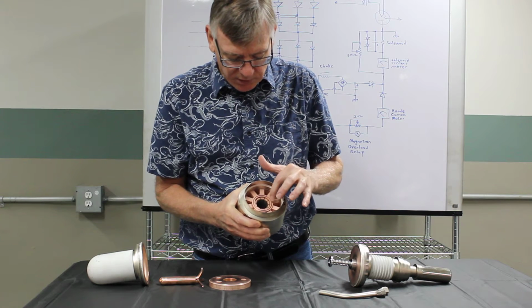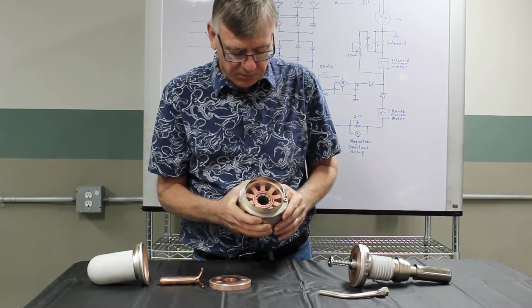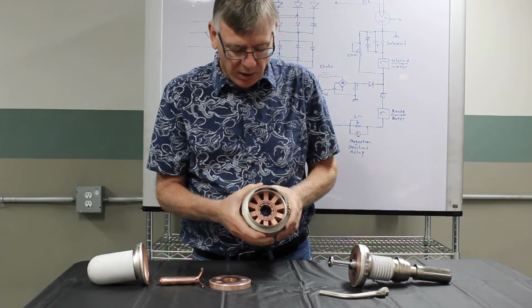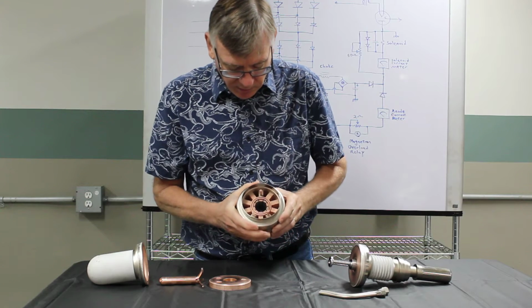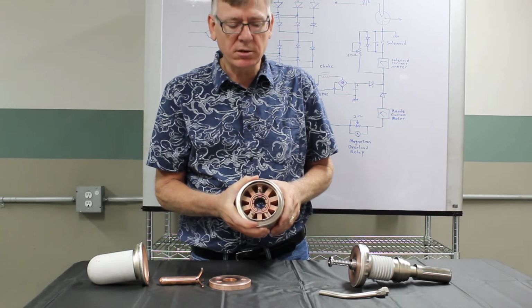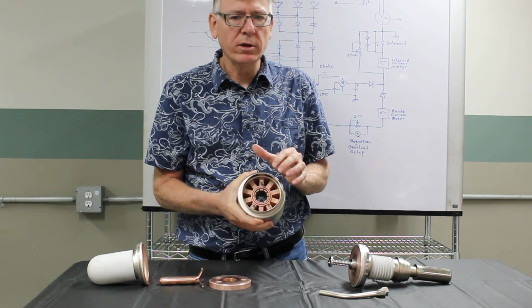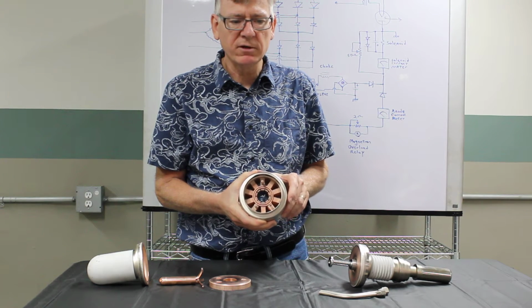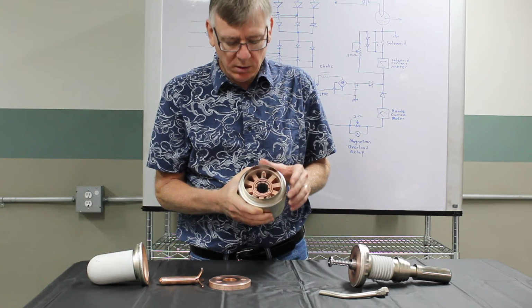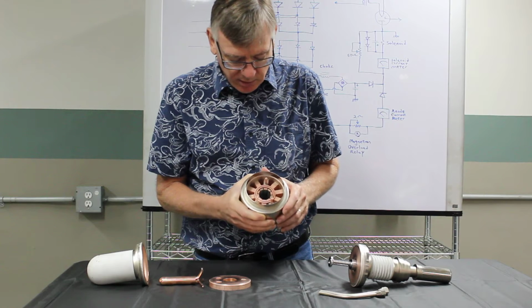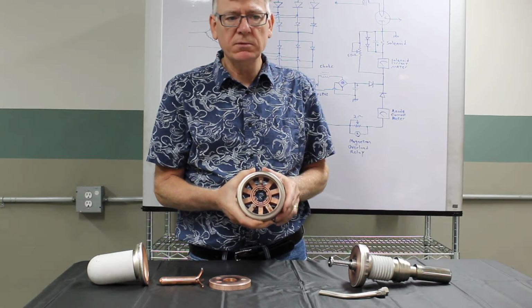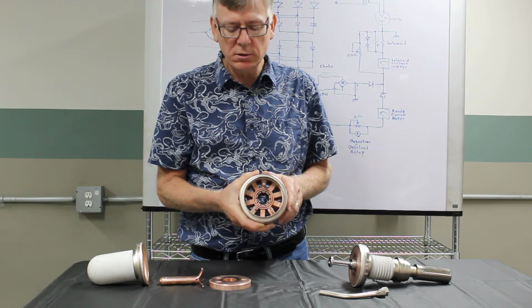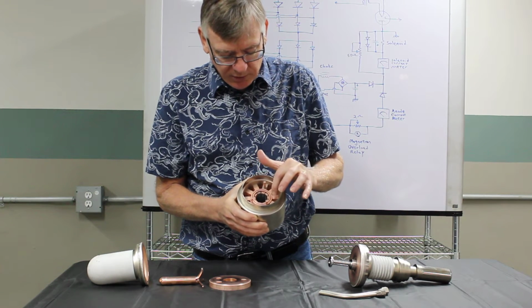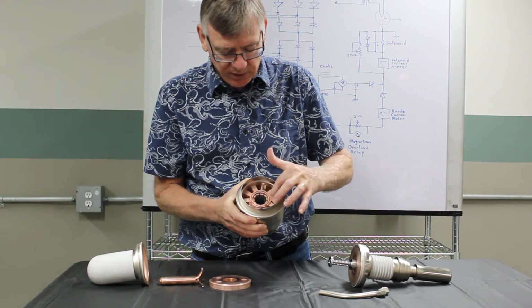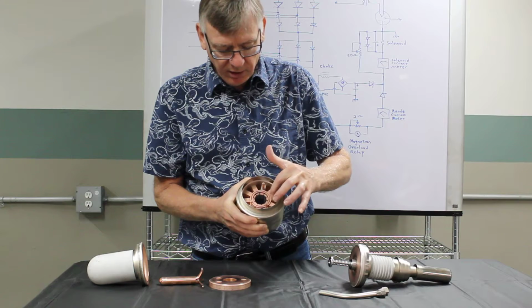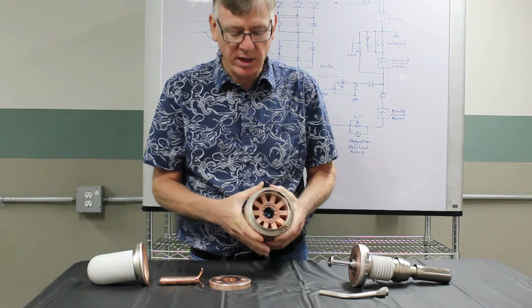And you'll see inside here there's a couple of little rings that go around the outside of the anode surface, and there's two on the other side as well. These rings, we call them mode locking straps, and they help make sure that the tube runs at 915 megahertz without shifting to some other frequency, which we don't want. When the tube changes frequency, we call that moding, and that can cause damage in the tube. These rings, or mode locking straps, are connected to alternate vane tips. So this outer ring is connected to 5, and the inner ring is connected to the other 5. And the same on this side. It's exactly the same on both sides.